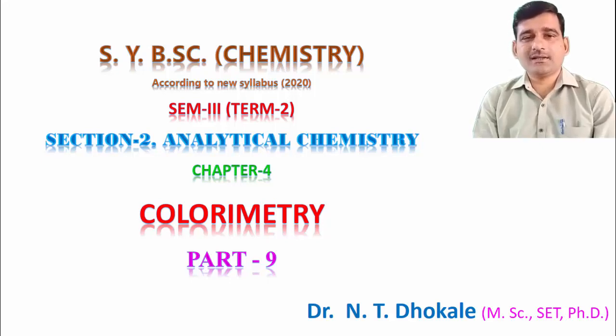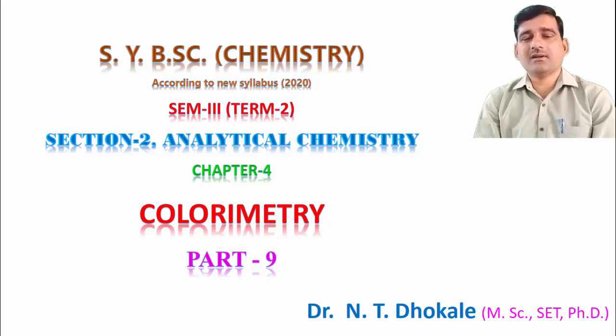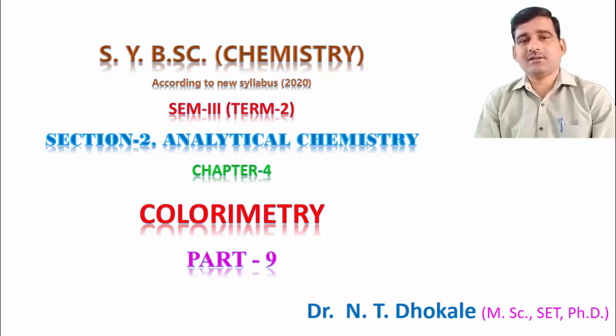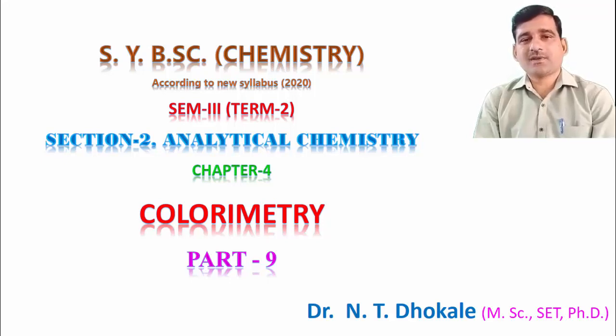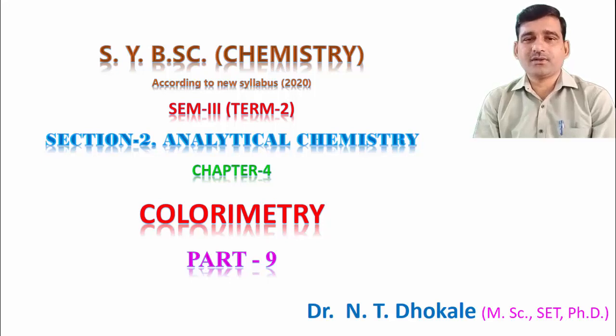For the visible region we can use a tungsten filament lamp. We discussed how the tungsten filament lamp is constructed, how it works, and its advantages and disadvantages. Instead of the tungsten filament lamp, we can use a carbon arc lamp for the visible region, and for the ultraviolet region we can use a hydrogen lamp, deuterium lamp, xenon discharge lamp, or sometimes a mercury arc lamp.